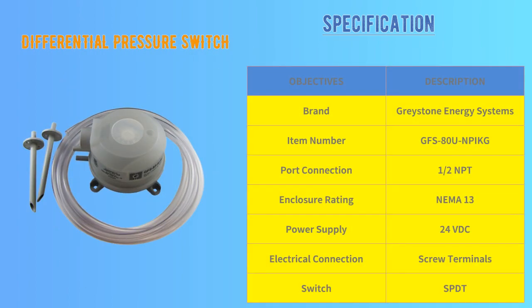Fifth, differential pressure switch, also called DPS. This is a product of Greystone. This field device is used for sensing pressure or sensing airflow. When there is no flow, it will give a dry contact signal to the controller and the equipment will stop immediately.